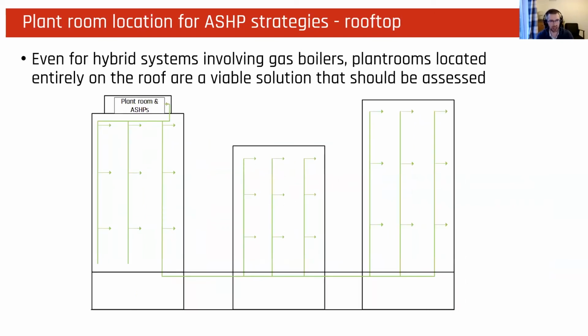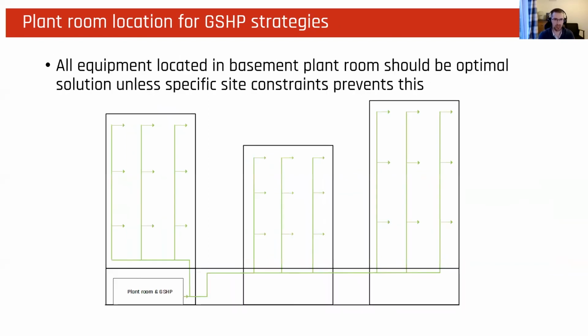However, something I wanted to highlight that is often discounted again too early, but is then brought back on the table when further constraints start to make the original energy strategy not really viable, is entirely rooftop package plant rooms, even for hybrid systems involving gas or electric boilers. Look at the space your solution needs. Try to understand whether actually it is a better solution for that all to go on the roof. You're removing a flue going through the building, potentially you've got to take the gas up there, yes, but there are pros and cons there. Sometimes this can be overlooked, but it's definitely worth considering at stage 1, stage 2. And with ground source, you're likely to have a single ground level plant room, trying to find the optimal location for that, and then distributing site-wide from there without any need for rooftop plant.